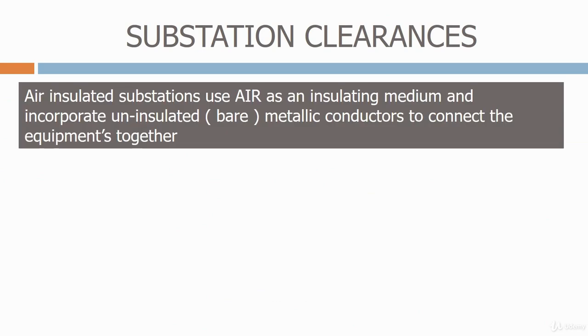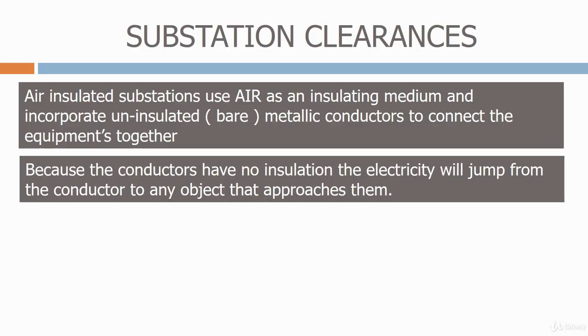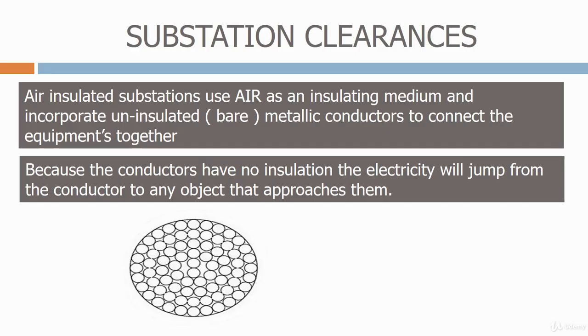Air-insulated substations use air as an insulating medium and incorporate uninsulated, i.e. bare, metallic conductors to connect the equipments together. Because the conductors have no insulation, the electricity will jump from the conductor to any object that approaches them. Here's a typical bare conductor. Once the object gets to within a certain distance of the live conductor, it will break down the air, an arc will be formed, and the object will become live.